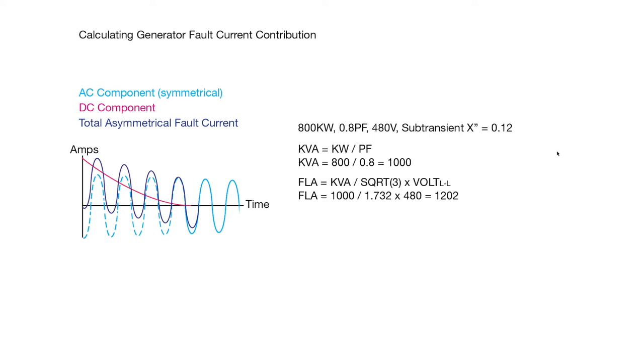Next we want to calculate the full load amps, or FLA. So we take the kVA and divide it by the square root of 3, assuming that it's a 3-phase generator, and we times it by the line-to-line voltage, which would be 480 in this case. And so we get an FLA of 1202.